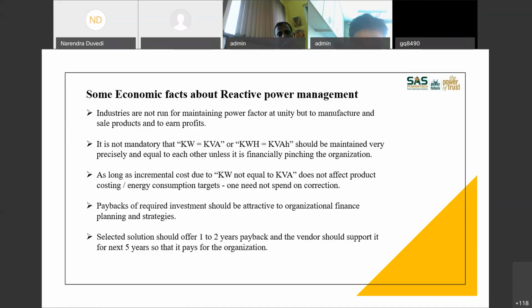Another thing, as far as support is concerned: typically APFC panels, whatever we have been using so far, were maintained by our own electricians, right? And we always used to say that no external agency is required for maintaining APFC panels. The moment you have an electronic solution, buying a 100 ampere active filter or harmonic filter or a static var generator of the same capacity, is probably like buying a 100 kVA UPS. All internal parts inside that panel are custom built by the vendor, and you will have to depend on him. I am not saying those solutions are not required, but they should be used optimally, for reasons which I will explain in the next few slides. So that's why this 5 years support is required.